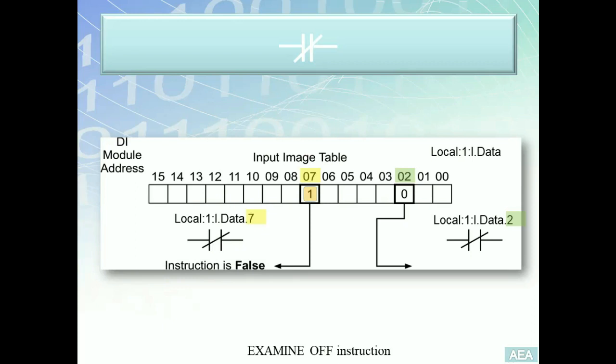Now moving to the XIO to the right. This one is examining bit number two. Similarly, I have no idea what type of switch is tied to terminal number two, but I know something for sure: this input is currently in the open state because it's reading logic zero in the PLC memory.